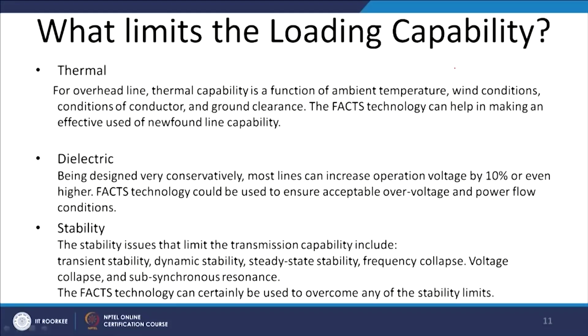Now, what governs these limits? One is thermal limits, and generally the thermal limit is designed considering the worst ambient condition, and the overhead line thermal limit is a function of the ambient condition, so there is a lot of leeway to take advantage of the present ambient condition. If we actively know the present ambient condition, then we can smartly overload the line, and thus the power handling capability of the line can be increased.